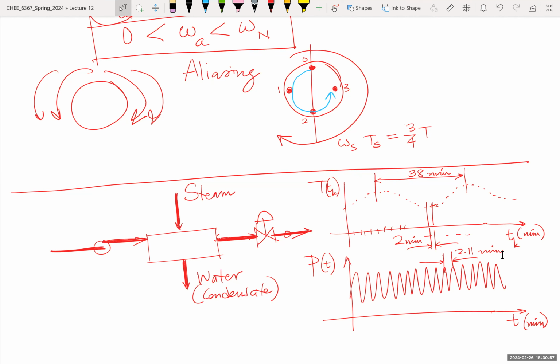But then again, if the valve goes up and down, up and down, and I see this change in pressure, that should indicate that the flow rate should have the same oscillation, right? And if the flow rate has the same oscillation, the residence time of the water that goes to that heater should change accordingly. And if the residence time of the water in the heater changes accordingly, shouldn't I suspect that the temperature at the outlet should change at the same frequency?